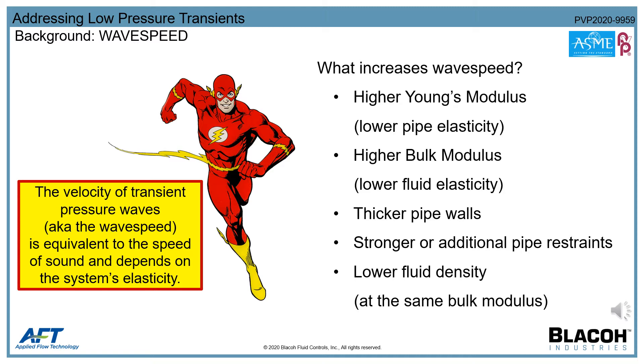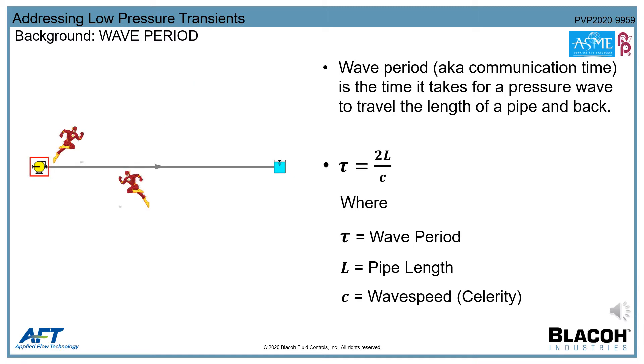In the case of low pressure transients, a higher wave speed will generate a larger drop in pressure. A transient wave's period, also known as the communication time, is essentially the time it takes the pressure wave to travel out and reflect back. When a wave reflects backwards, it can bring some relief to the initial pressure rise or drop. Generally, systems with longer wave periods tend to experience more significant surge spikes and dips, because the full extent of the velocity change is realized before the relieving wave returns.